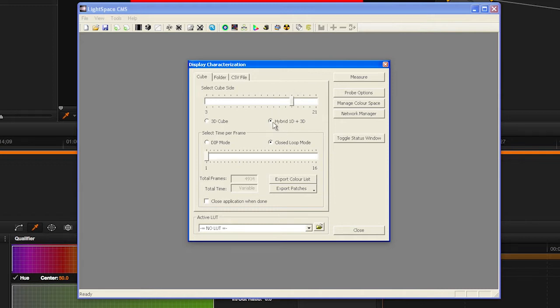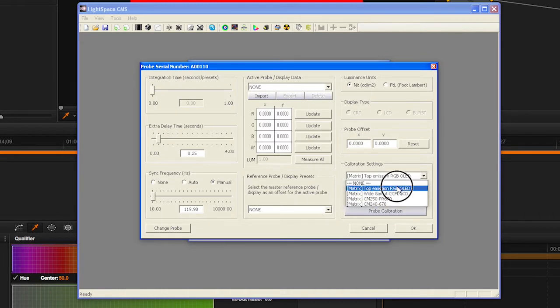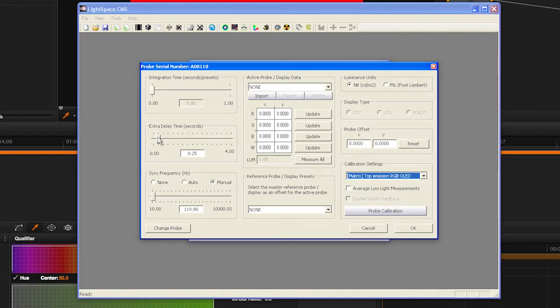Next, click on the probe options to set your integration time, if applicable. Extra Delay, we suggest 0.25, Sync Frequency, if applicable, and Calibration Settings, if using a colorimeter.